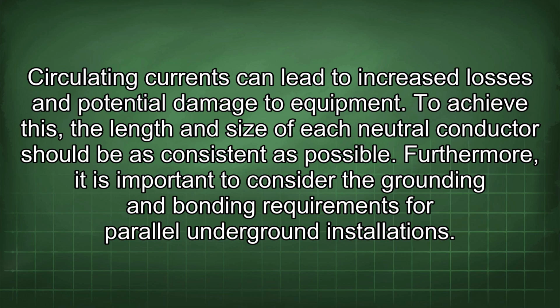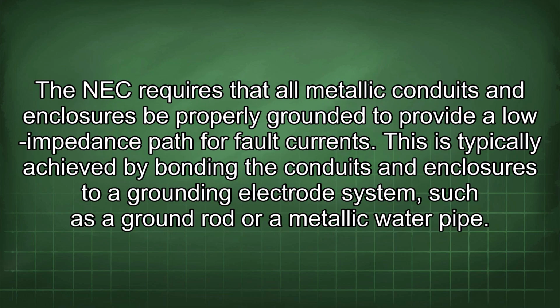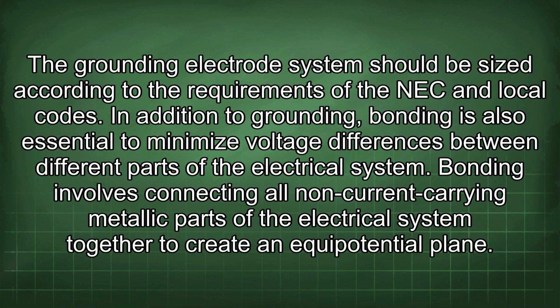Furthermore, it is important to consider the grounding and bonding requirements for parallel underground installations. The NEC requires that all metallic conduits and enclosures be properly grounded to provide a low impedance path for fault currents. This is typically achieved by bonding the conduits and enclosures to a grounding electrode system, such as a ground rod or a metallic water pipe. The grounding electrode system should be sized according to the requirements of the NEC and local codes.